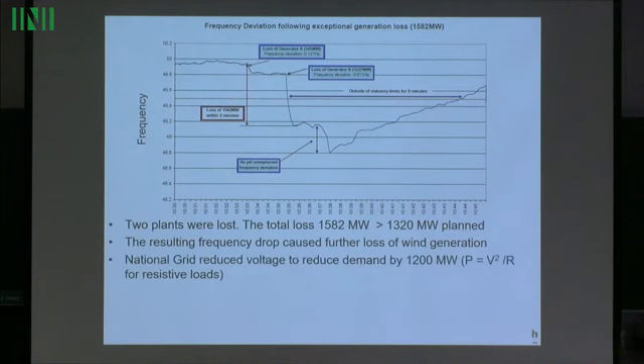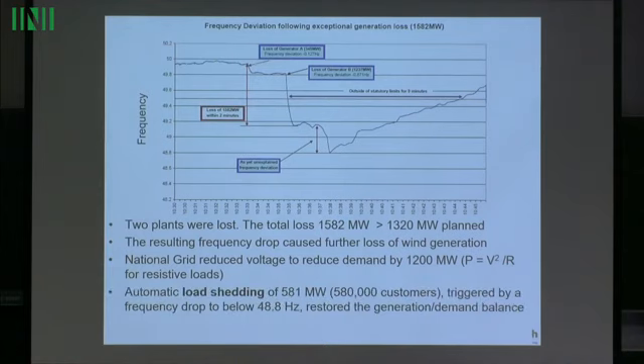So what happened then? When the frequency was dropping, National Grid reduced voltage because they could see what's happening. You see the time scale over here is about 2 minutes, so they could do something about it. So they started to reduce voltage artificially in the whole system. A lot of power is heating, which is resistive. So you reduce the voltage, power demand is V squared over R, so you reduce the demand.